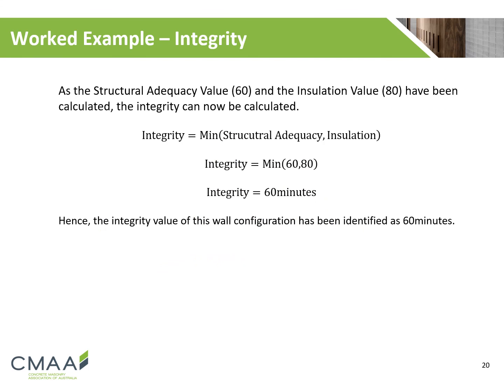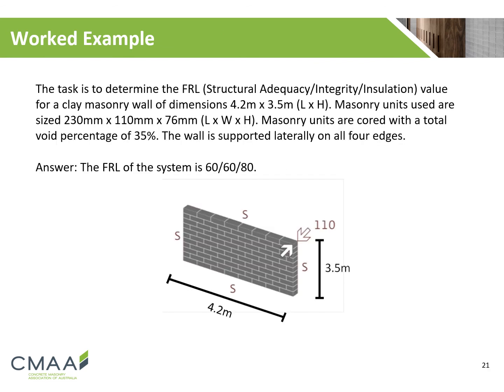Determining the integrity value is now a simple task as we know the structural adequacy and insulation values. Selecting the minimum of the two, we determine our wall integrity value to be 60 minutes. With that, we've now evaluated the FRL design for our masonry wall. It would be presented as a 60-60-80 wall when labelled using NCC terminologies.